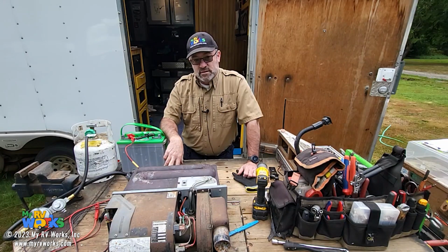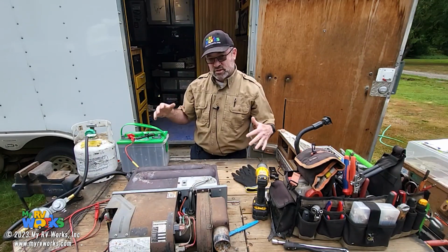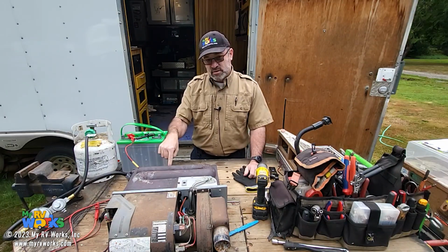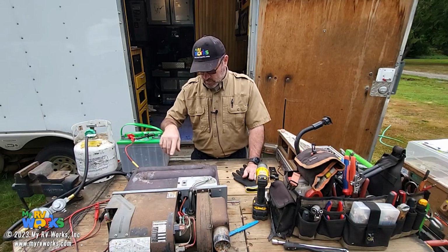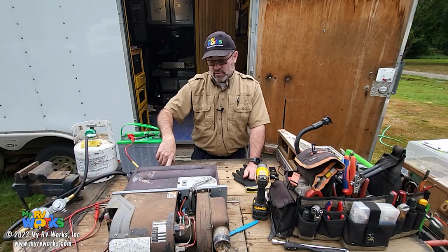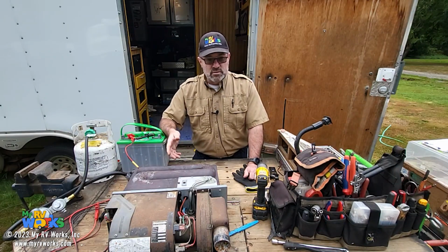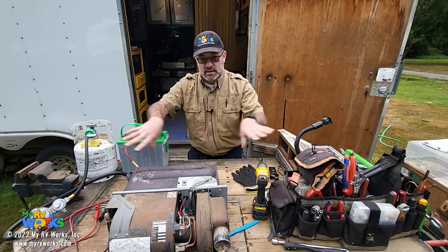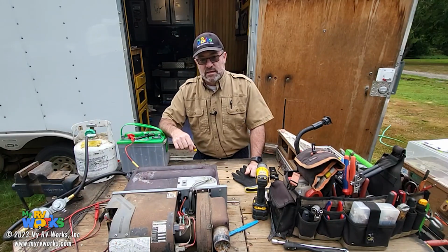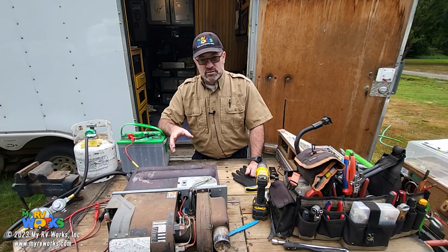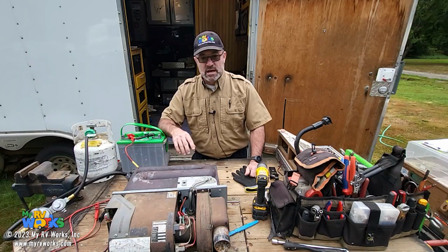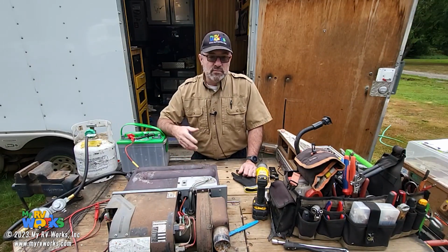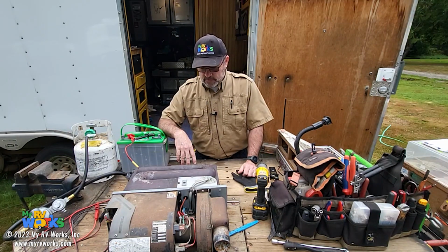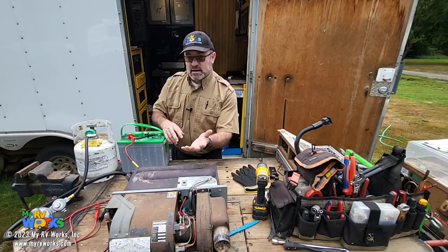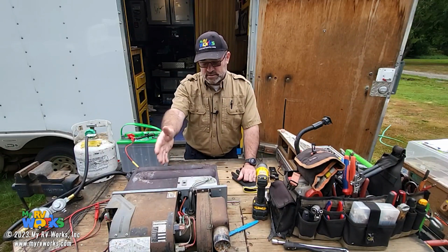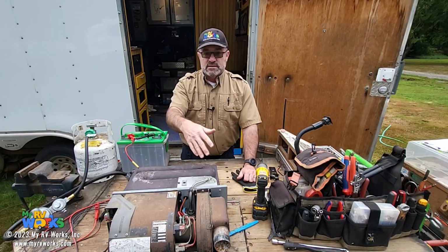So if your furnace is blowing heat out and it's got some restriction in the ductwork, then all that heat's backing up and it's going to trip this high temperature switch, which is here in the back. Then the furnace will extinguish the flame, cool down, and start back up again. We see that an awful lot. I've got a bore scope and I've put it inside some RVs where these ducts go through and come up on the floor. I've shown inside where the ductwork the manufacturer used has crushed or come untaped, or it's just not a nice smooth flow. That's unfortunate, because it's really difficult to get in there and fix that kind of stuff. But we do see it from time to time, and that causes the heat to back up inside the furnace. So if your high temperature switch trips, that would cause this furnace to intermittently extinguish itself and light itself, extinguish itself and light itself.